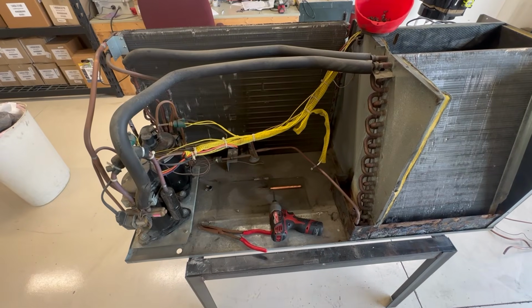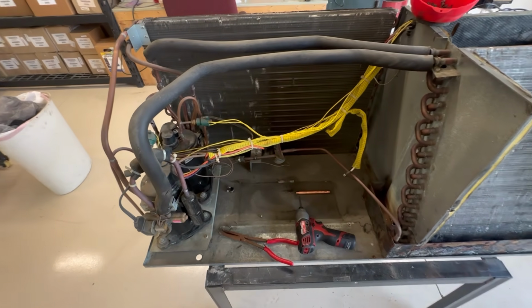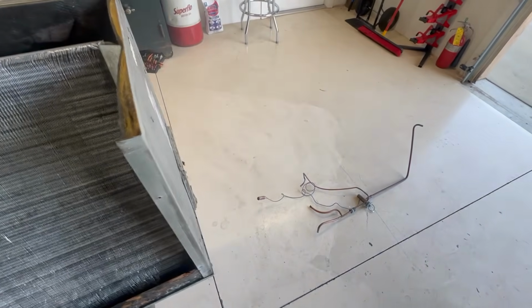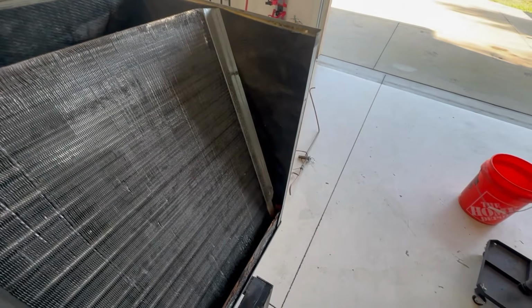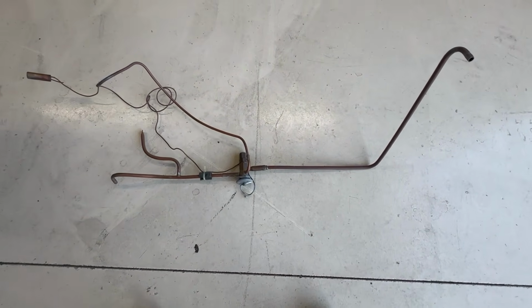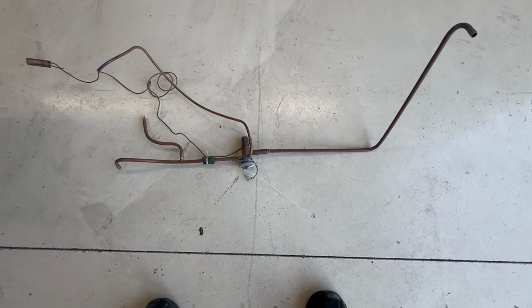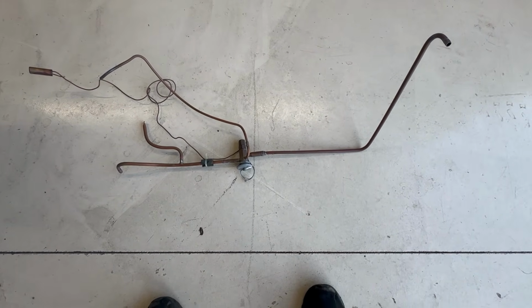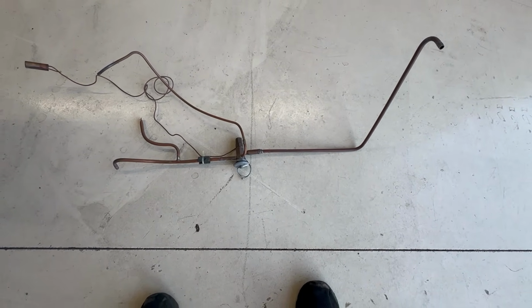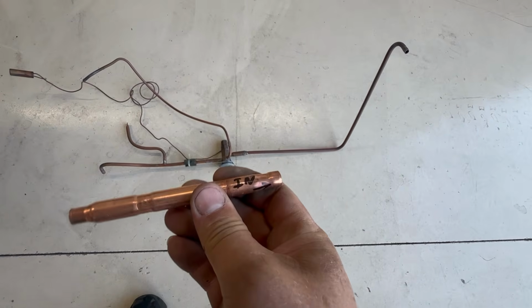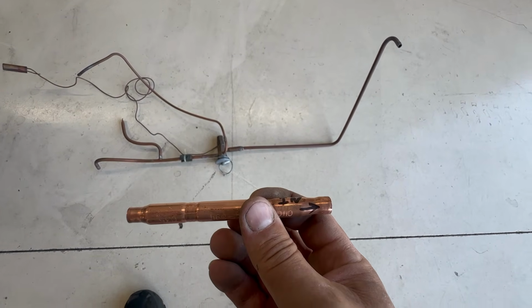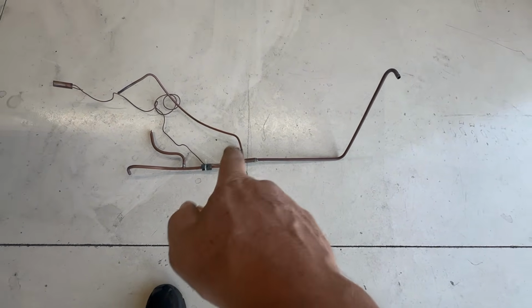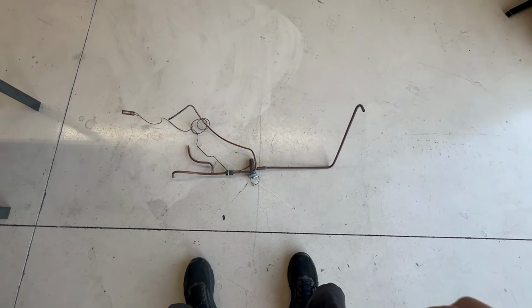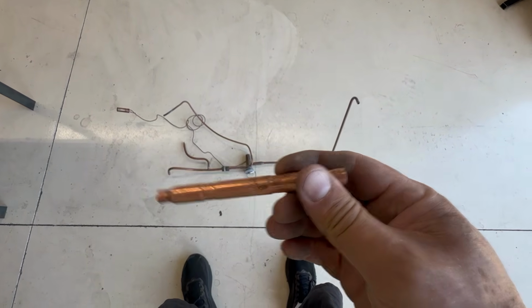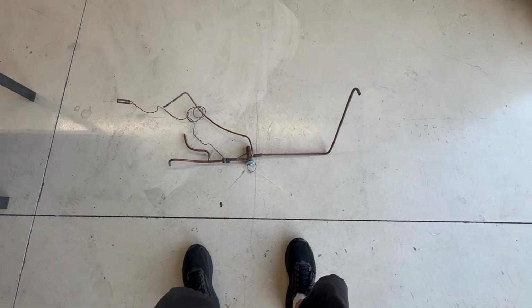So this 46516, you see I've got it opened up. It does have a bad compressor. This right here is the thermal expansion valve assembly that I take out of this, because that's no longer available through Coleman. And I'm not a real big fan of those anyways, because this is what we're going to put in its place, is a Bi-flo valve, which solves a lot of problems we got going on there. So I've got that one out, and I'm going to go ahead and fit this in its place, and then we're going to get the compressor swapped out.